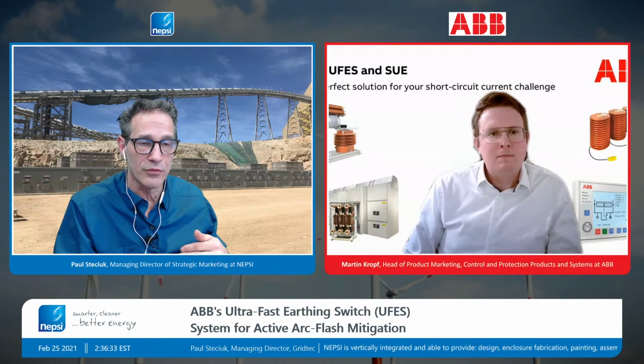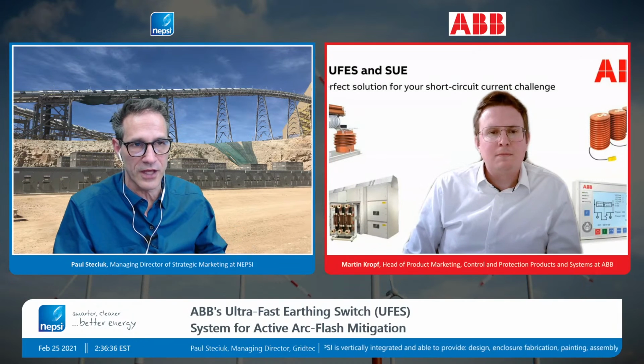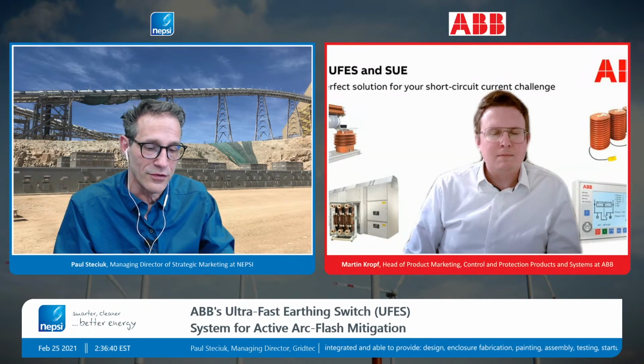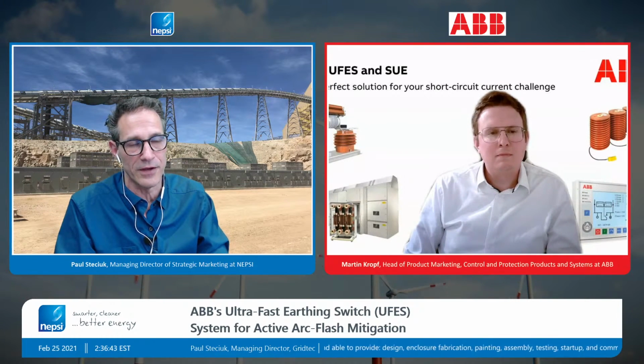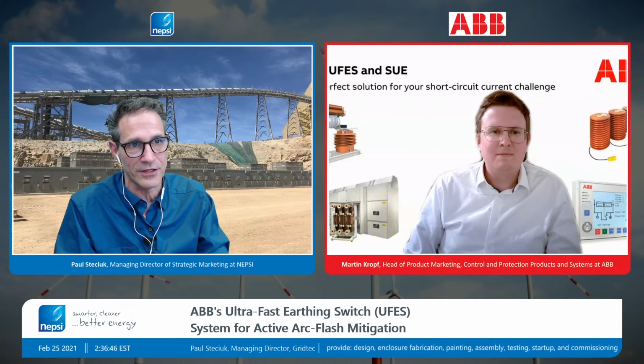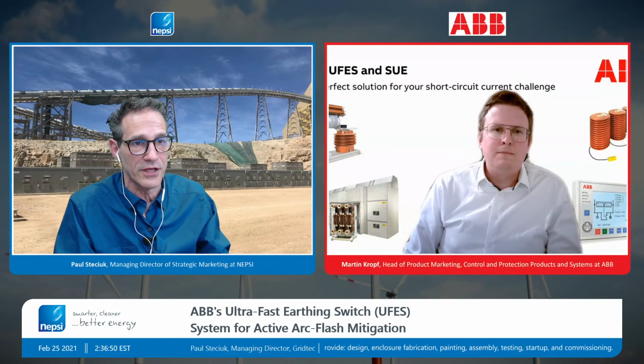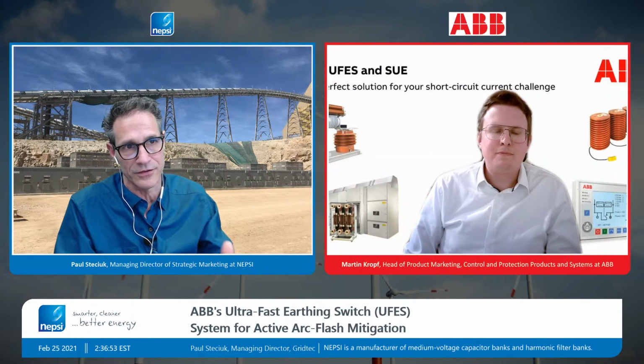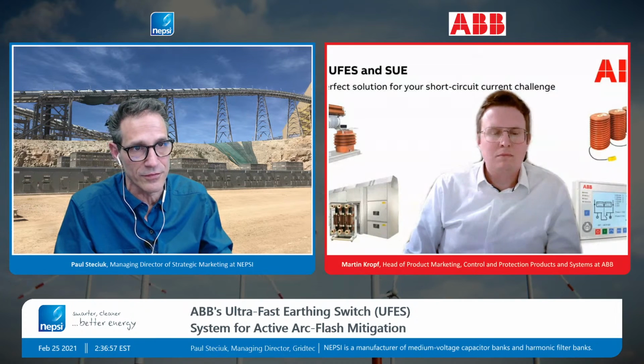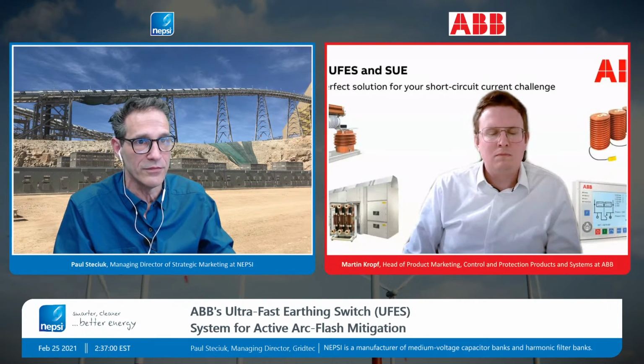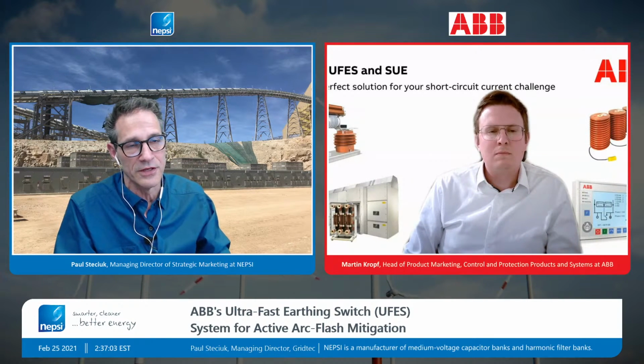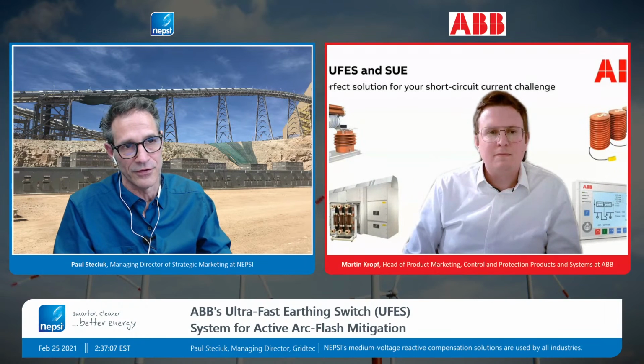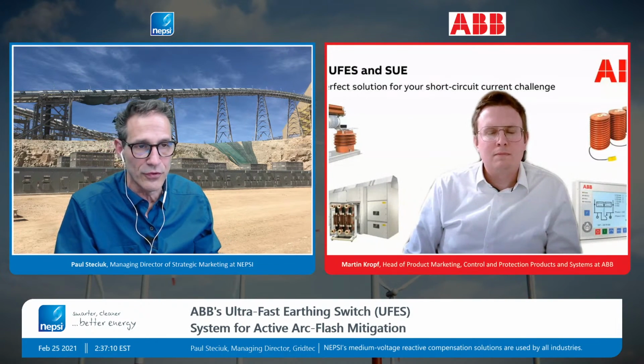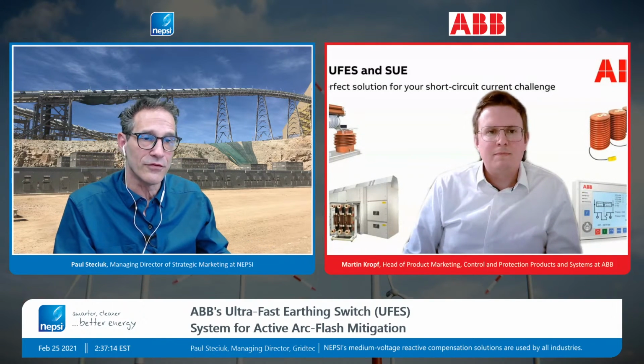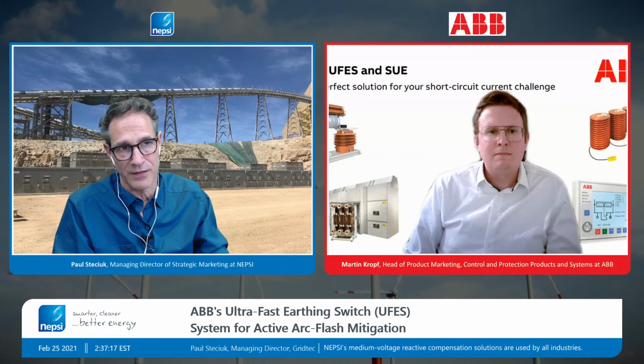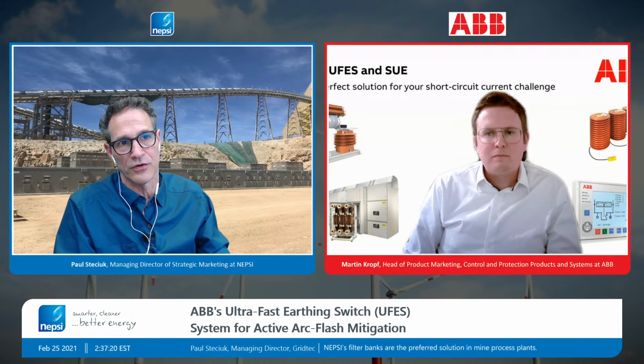From our custom gear standpoint, we produce cap banks and filter banks. Oftentimes when you think of arc flash mitigation, you think about switchgear. But the reality is that this active arc flash mitigation system should be installed in a lot of other components like rectifiers and drive systems. These devices are all very expensive. They can be $500,000, $1 million each or more, and critical to operations. So having the ability to detect an arc and eliminate the equipment damage is very important. It should be looked at for other components outside of switchgear and even outside cap banks and filter banks, anything that's electrical and critical to a process.